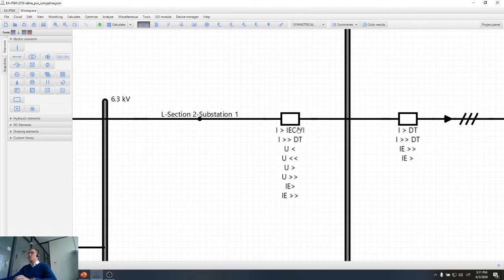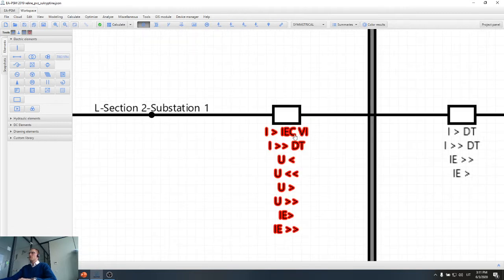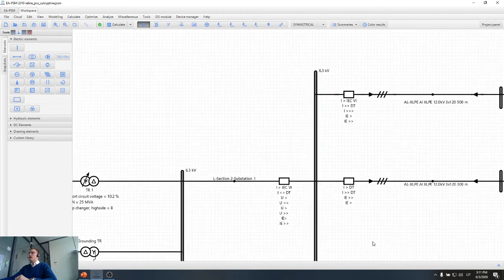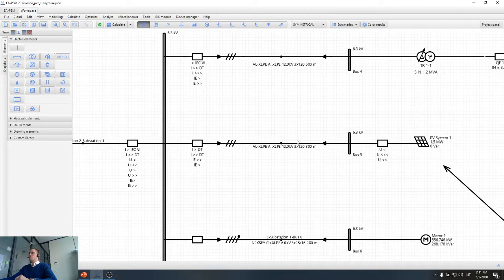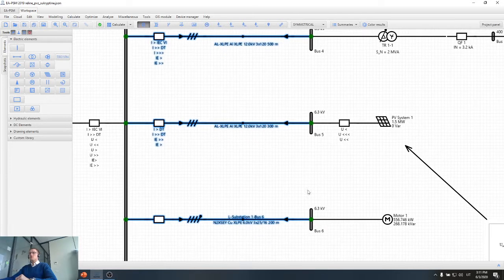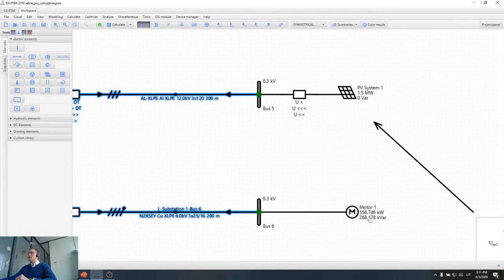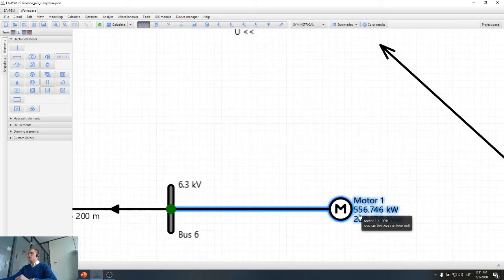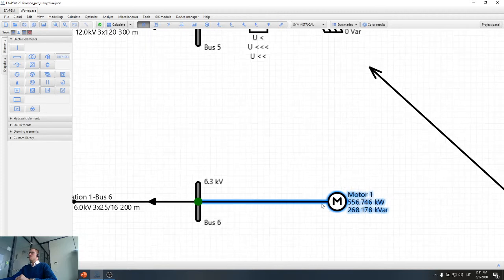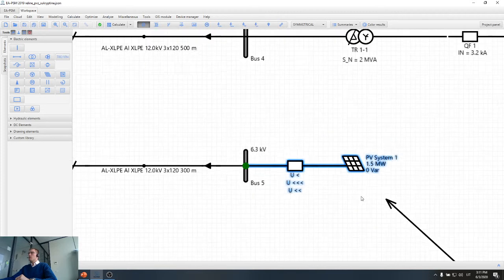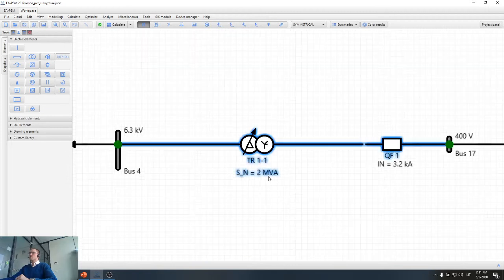Then we have a breaker already with quite a few protection functionalities. Here are 2 stages of overcurrent protection devices, then under voltage, over voltage, and ground fault protection 2 stages as well. So here we have also a 6.3 kilovolt network consisting of 3 cables, 500, 300 and 200 meters in length. And we also have some equipment connected, like a powerful over 500 kilowatts motor. Then there is a solar power plant, 1.5 megawatt, and one 2 megawatts transformer.